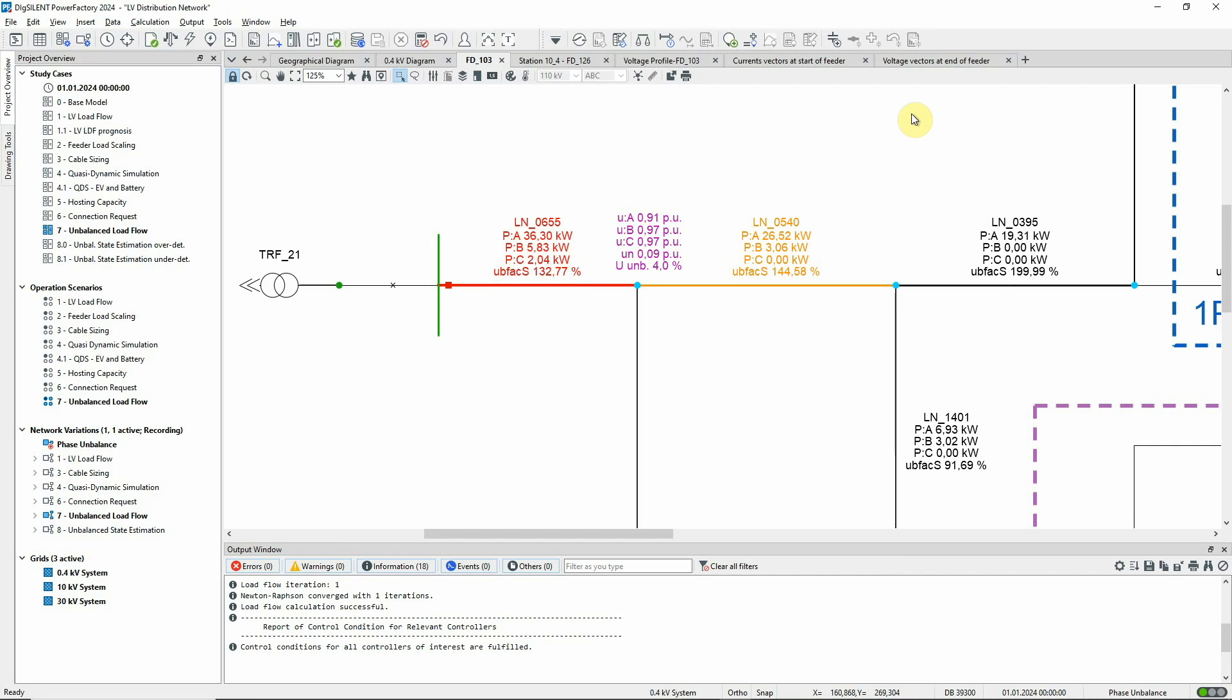It can be seen that the power imbalance in the line is quite high. For the terminal, we can see the voltages of all three phases and the neutral conductor to earth, together with the imbalance factor of the voltage. This factor reflects the ratio between negative and positive sequence voltages and is quite large in this case.